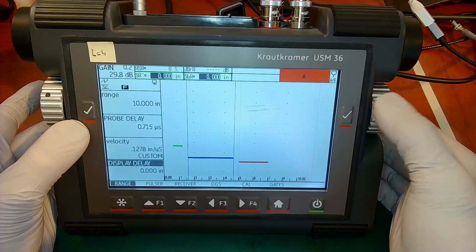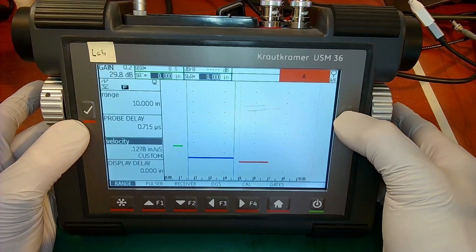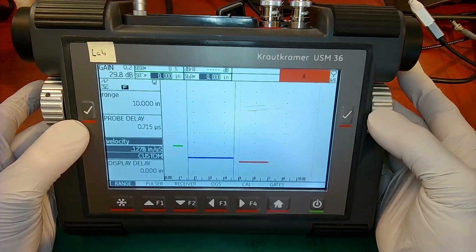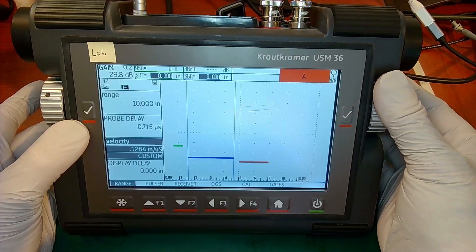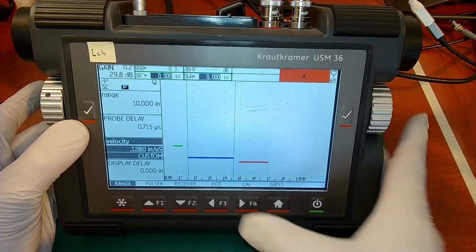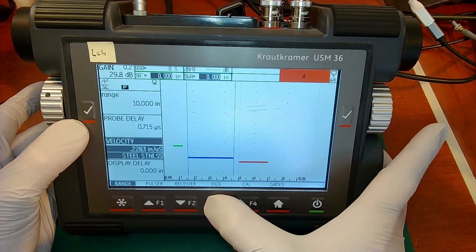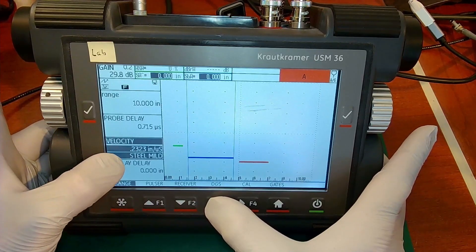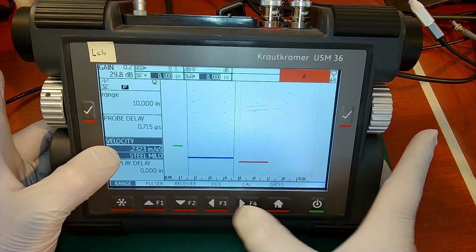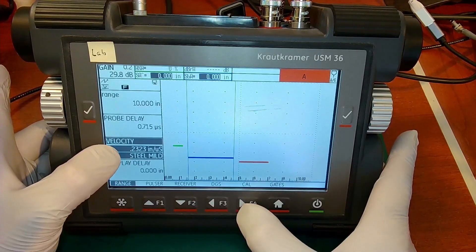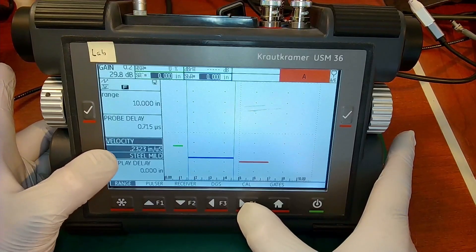If I go to my velocity parameter and select that, I can either adjust the velocity in small increments, or by using the right and left arrow keys, I can parse through a list of materials and see the known or stored velocity for that material. So with the right and left arrows, I can select mild steel, shear velocity.